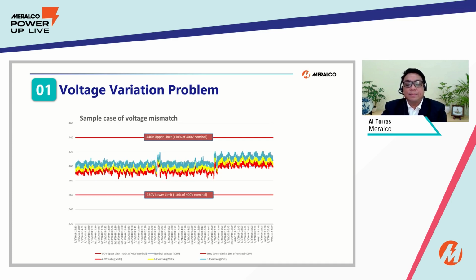So let me illustrate a sample voltage variation problem brought about by a mismatched equipment rating. Say this is a voltage variation of a 400 volt supply. The red lines are the upper and the lower limit, and lines 1, 2 and 3 are the red, yellow and blue lines. We can say that the voltage is normal and within the plus minus 10% limits. So we can assume that the equipment will operate satisfactorily given these voltage values.